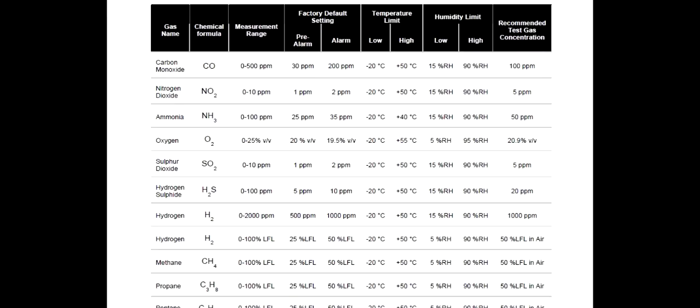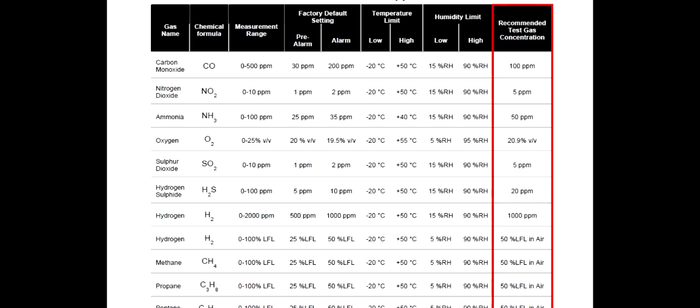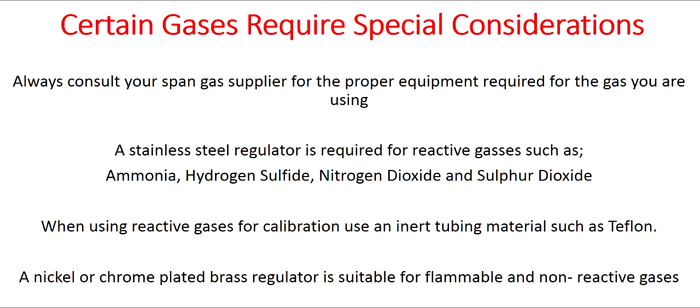To choose the proper span gas concentration, please refer to the ECO product guide, Appendix A. Toxic gases are referred to in parts per million and flammable gases are referred to in percent lower flammable limit. Certain gases require special considerations. Always consult your span gas supplier for the proper equipment required for the gas you are using.